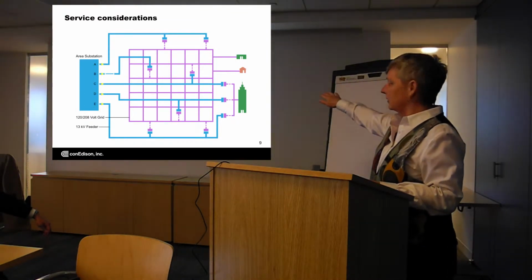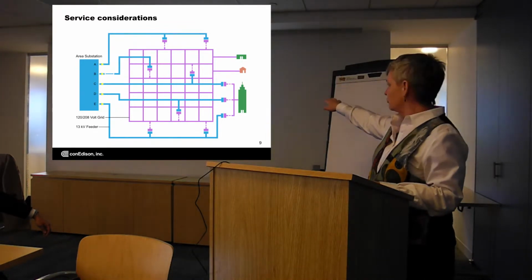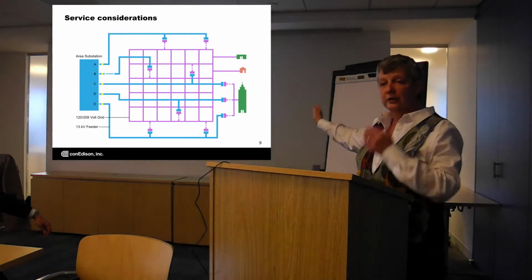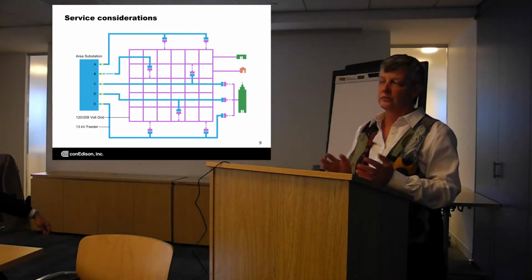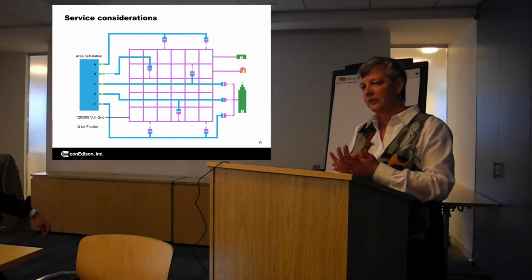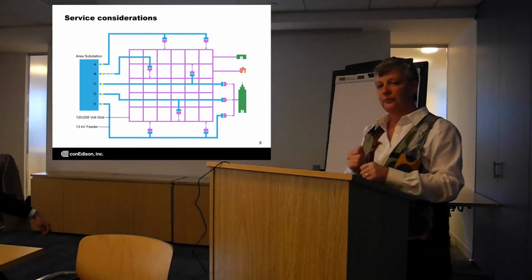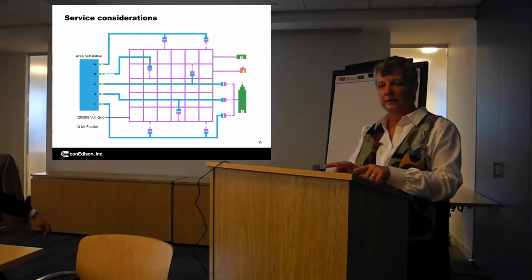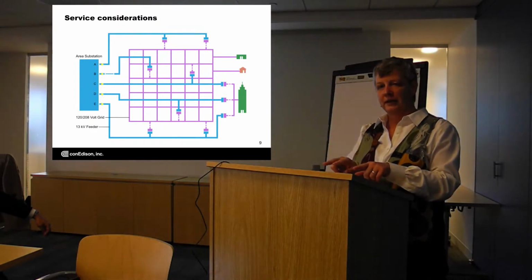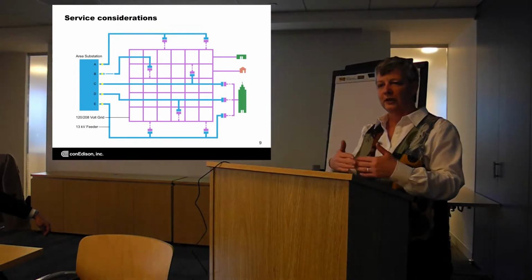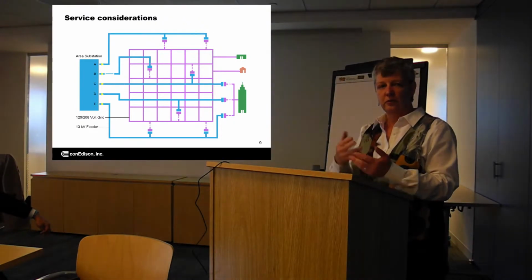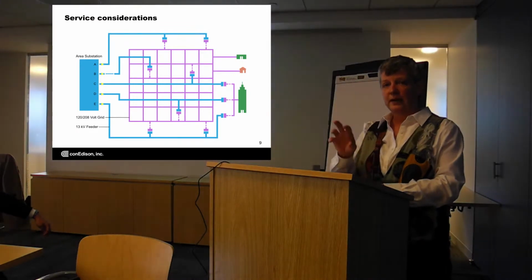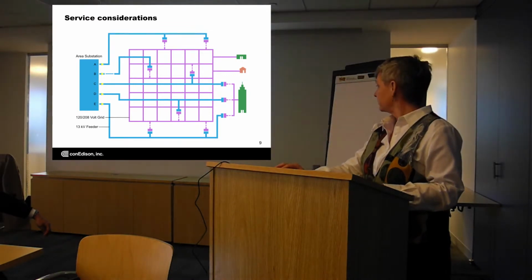So you can have a building that comes right off that grid, which is shown up on the right, commercial or residential. And for a very large customer, I would say above maybe 2 megawatts in size, you may have these blue feeders that are dedicated to that building, dedicated transformers, dedicated network protectors, and then the transformation happens to this 120-208 or 460 volt distribution system at that larger complex.